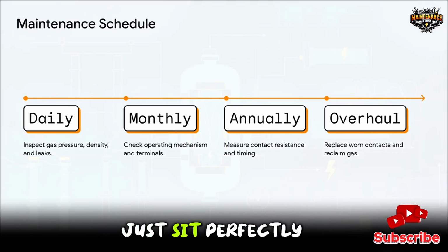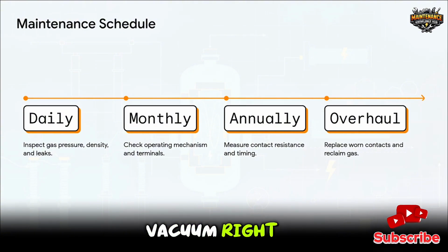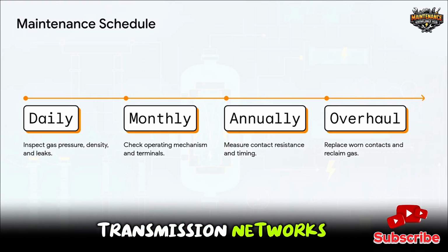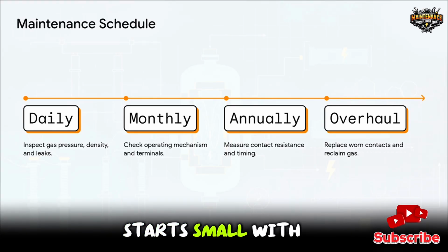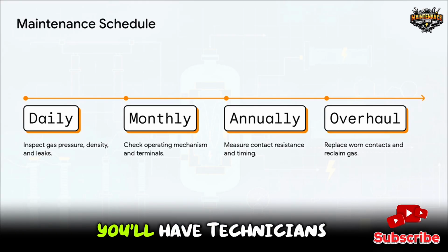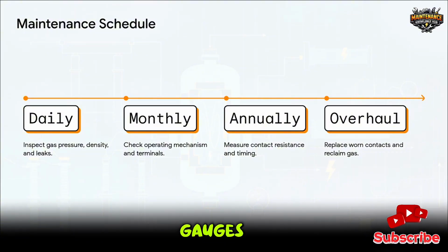Up next is Section 5, Maintenance and Troubleshooting. These machines don't just sit perfectly untouched in a vacuum, right? They battle the elements every single day, protecting entire power generation plants and massive regional transmission networks. So the life cycle of preventative maintenance starts small with daily visual inspections. You'll have technicians out there checking the pressure gauges, verifying alarms, and just listening. Literally listening for any unusual hiss of a leak.